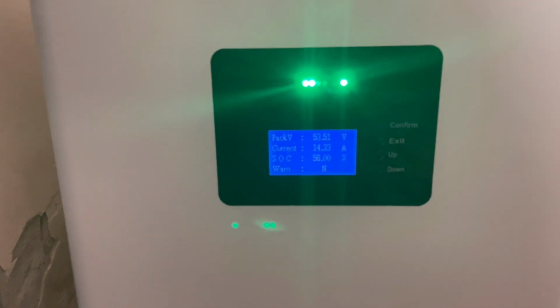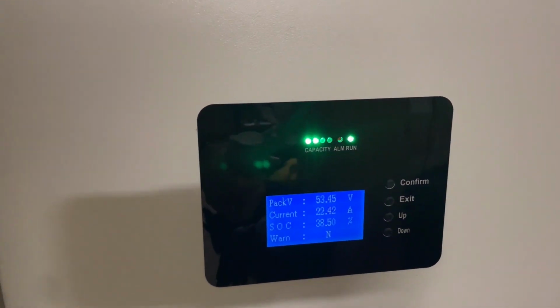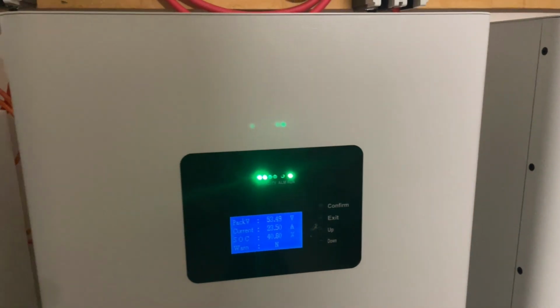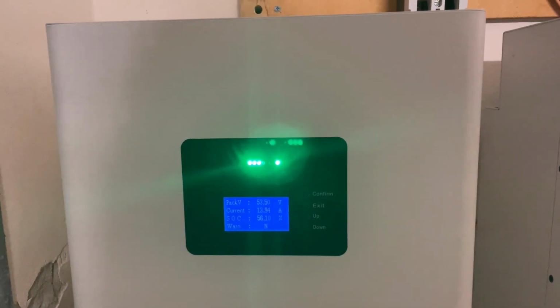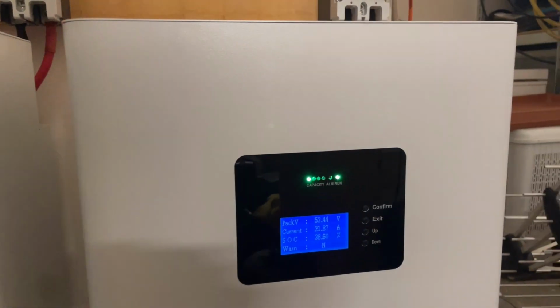If you look at the current going into the third battery bank, it's 14 amps. The secondary is 23, and the primary is 22. So that tells me the BMS is trying to bring the primary and secondary battery banks up to the same level of charge as the third battery bank. 16% higher state of charge on the third battery bank than the secondary, and the primary is only at 38.6% charge.